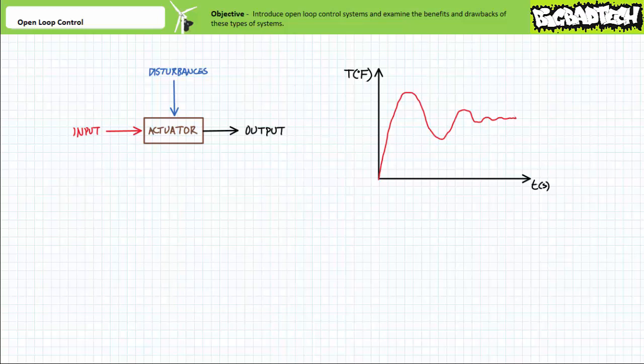An excellent example of a tuning procedure used to adjust an open-loop control system is the acceleration and deceleration control using proportional valves lecture available at the Big Bad Tech channel. That lecture featured an iterative tuning process whereby a technician progressively adjusted the ramp time produced by the proportional valve controller, and thereby the acceleration and deceleration characteristics of the applied load. Through careful observation, the system was properly adjusted such that the applied load underwent controlled acceleration and deceleration, the cylinder fully extended and retracted, and pressure spikes were minimized. It took four attempts and careful human observation to yield the desired result.